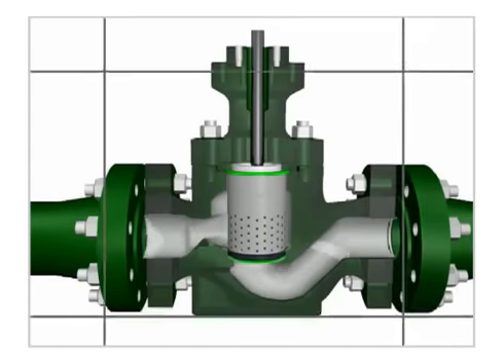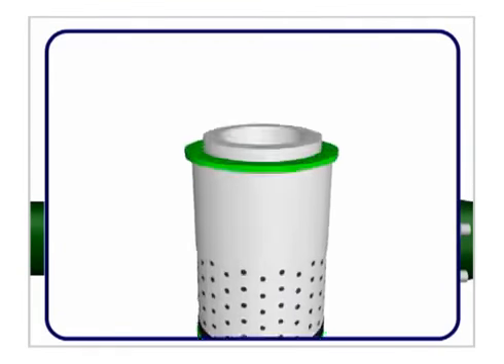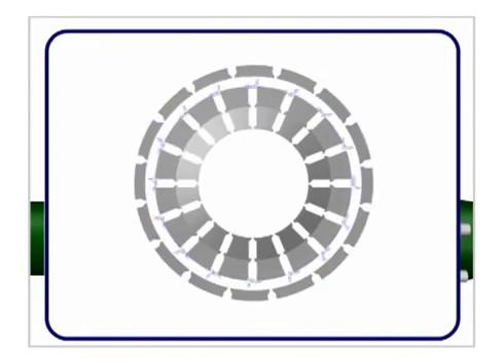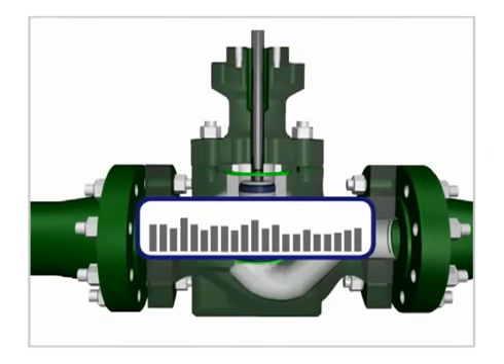For example, in the Cavitrol III valve trim, nozzles have holes shaped to manage flow separation. Multiple small holes shift the noise to higher frequencies.